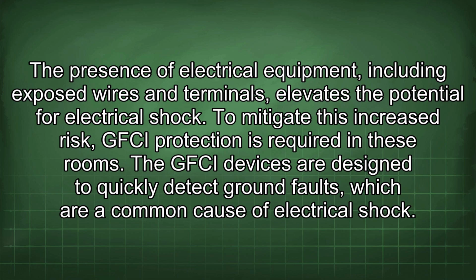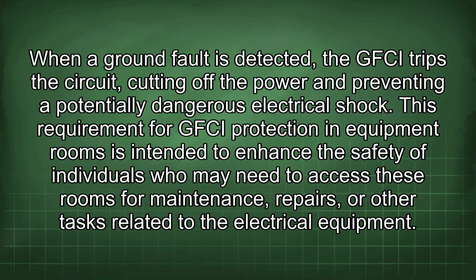The GFCI devices are designed to quickly detect ground faults, which are a common cause of electrical shock. When a ground fault is detected, the GFCI trips the circuit, cutting off the power and preventing a potentially dangerous electrical shock. This requirement for GFCI protection in equipment rooms is intended to enhance the safety of individuals who may need to access these rooms for maintenance, repairs, or other tasks related to the electrical equipment.